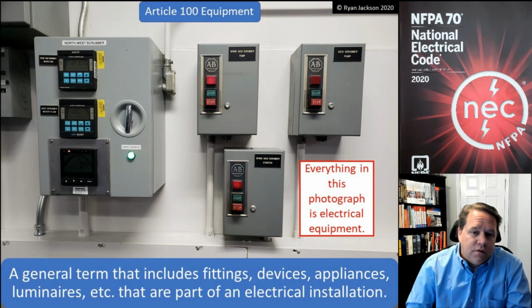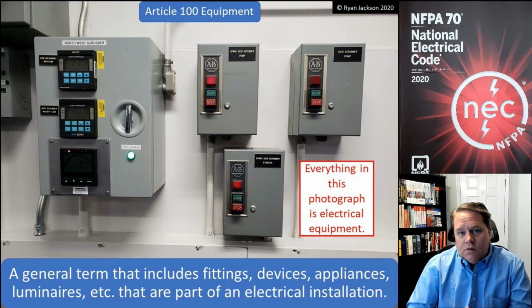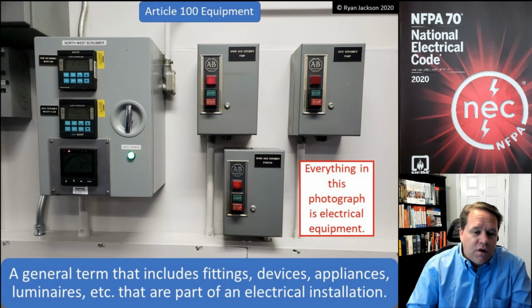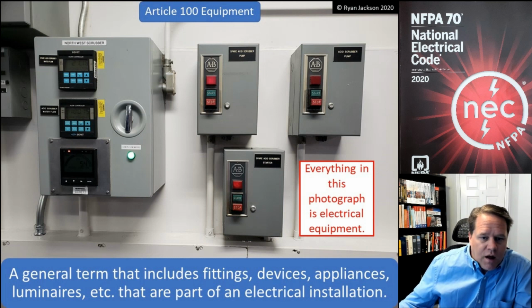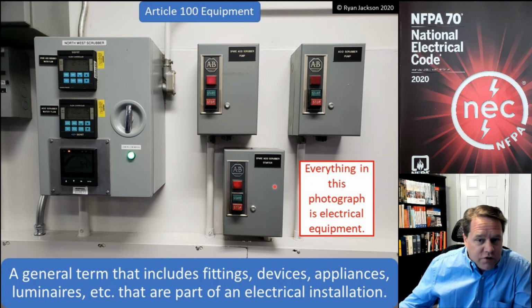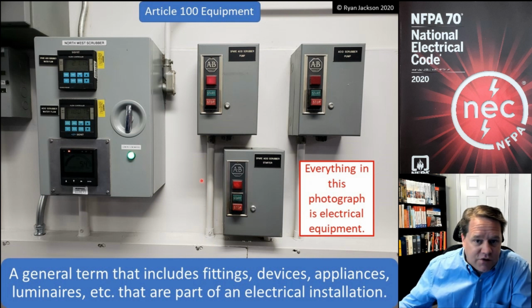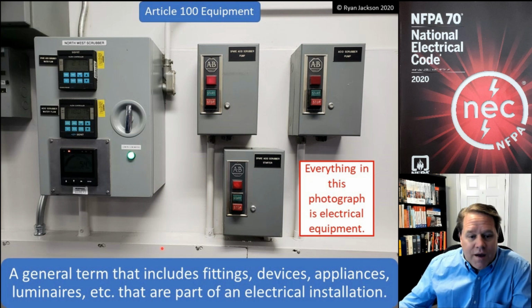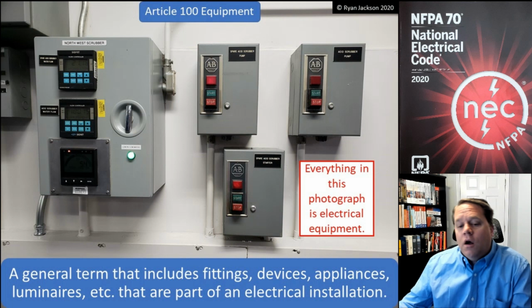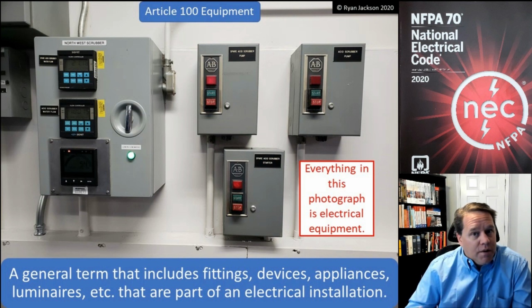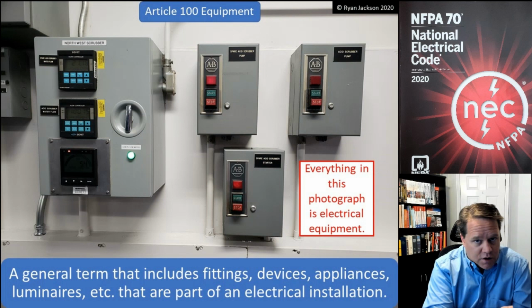In this photograph, every single thing you can see, other than the wall itself, is electrical equipment. This looks like maybe an adjustable speed drive, which is electrical equipment. The controllers here, these stop-start stations, these are equipment. The raceways between the controller and the wireway are equipment. The fittings are equipment. The straps that are missing are equipment. The wireway down here, and by the way, that's a wireway, not a gutter, is equipment. Everything we install is conductors or equipment.